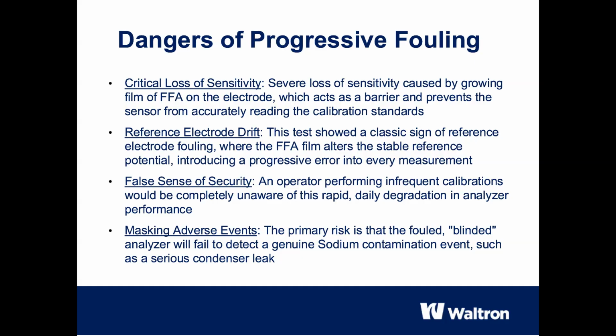Third, and this is the crucial point for the operator, it creates a false sense of security. An operator who calibrates infrequently would not notice this rapid daily deterioration. The instrument appears to be working, but provides unreliable values. The greatest danger is the masking of malfunctions. The primary purpose of a sodium analyzer, for example, is the early detection of a condenser leak. A contaminated, blinded analyzer will not report such a critical event, or will only report it much too late.